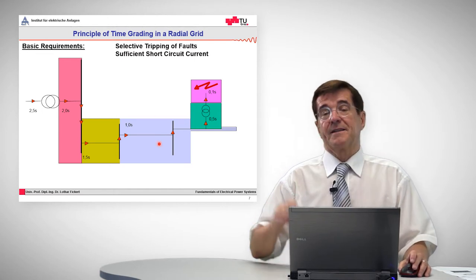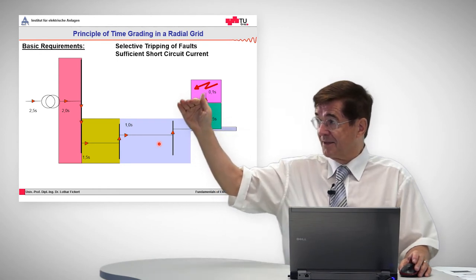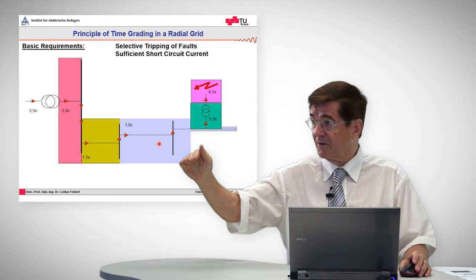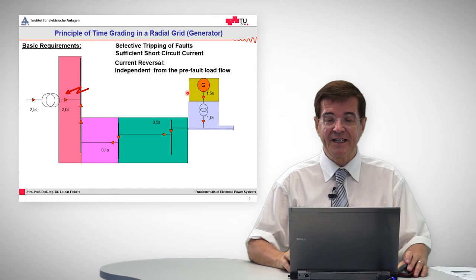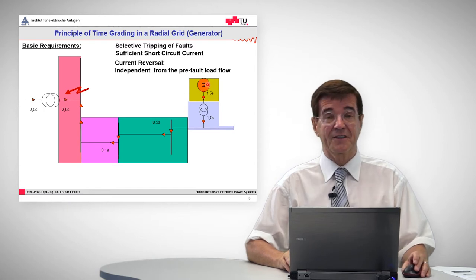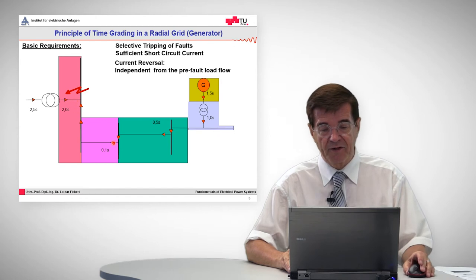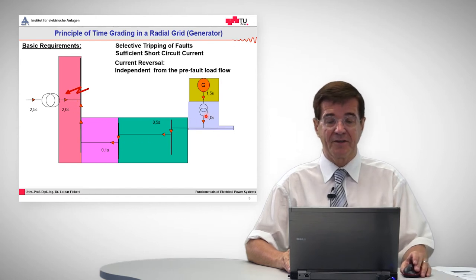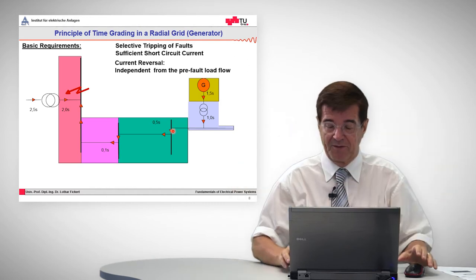The principle is that the grading, the time grading, increases from the last point of the grid to the source. When in contrast one changes the infeed so that another source is at the end of the grid, then one would need exactly the reverse order of timing. These protection times are graded in the opposite way and that may cause problems.